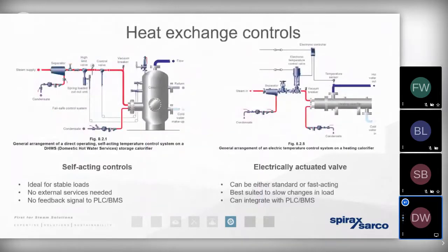So I want to go back to that traditional storage calorifier again, as you can see over towards the left-hand side of the screen. That's going to be typically supplied with self-acting valves that operate on that proportional control. And that's all well and good. That'll work efficiently. Because we've got that storage of hot water on the secondary side, it's far, far more stable. The release of energy across the heat exchanger is going to be more stable.